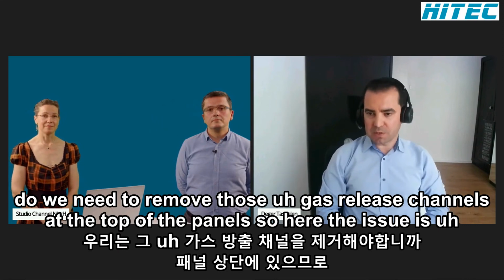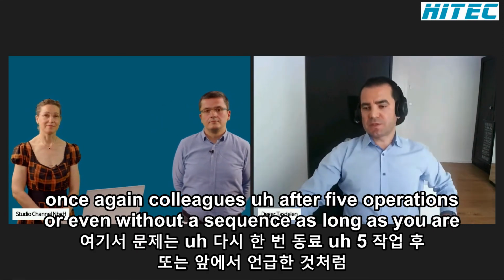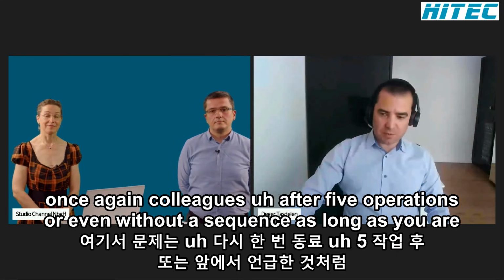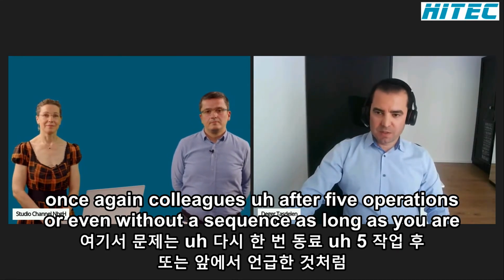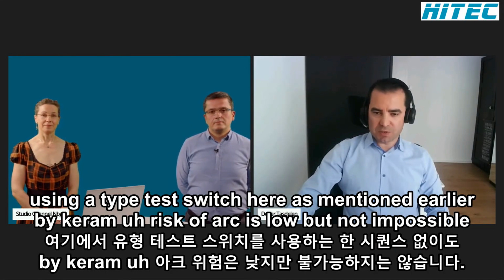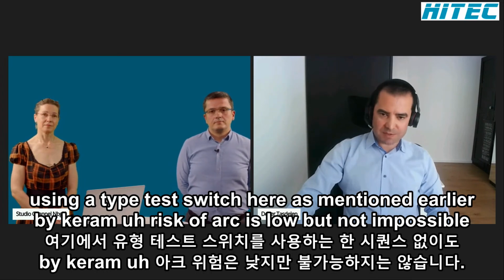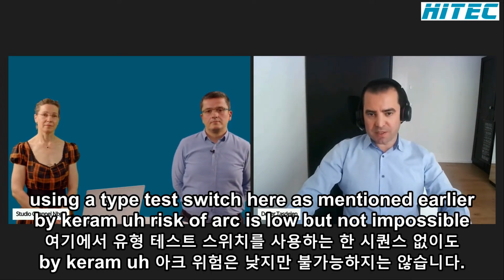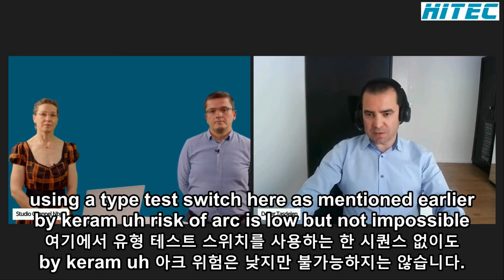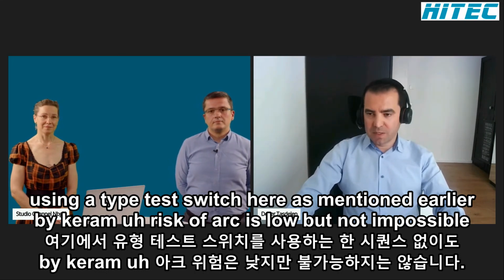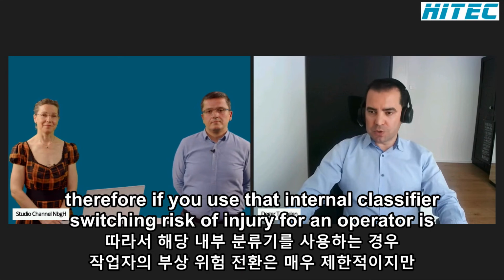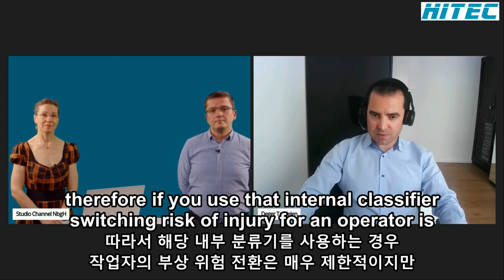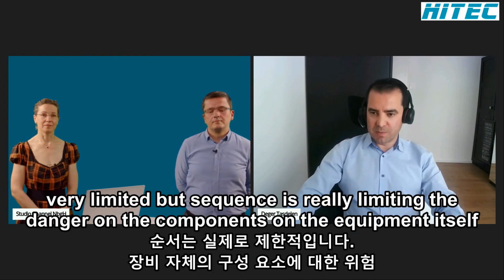So here the issue is, once again colleagues, after 5 operations, or even without a SIQuench, as long as you are using an internally classified, type-tested switchgear, as mentioned earlier, the risk of an arc is low, but not impossible. Therefore, if you use that internally classified switchgear, the risk of injury for an operator is very limited, but SIQuench really limits the danger to the components, to the equipment itself.